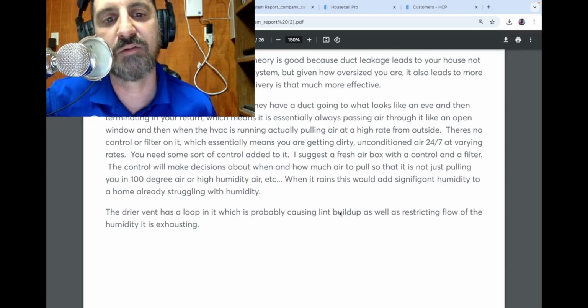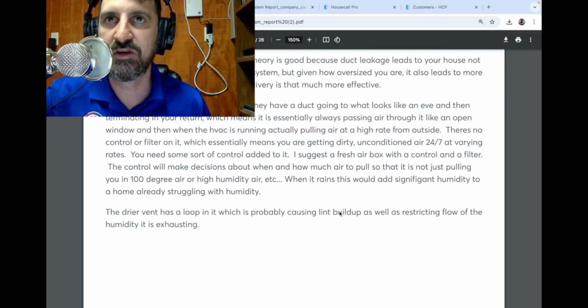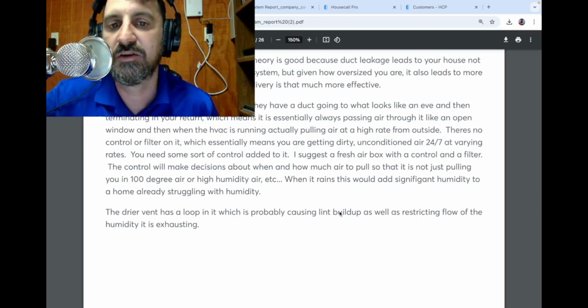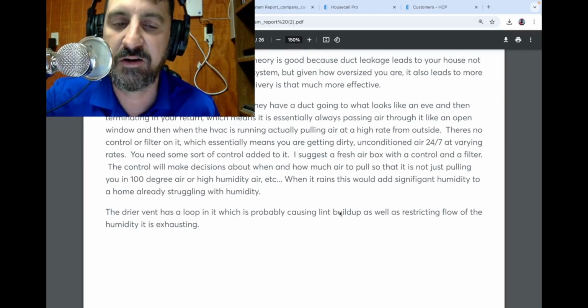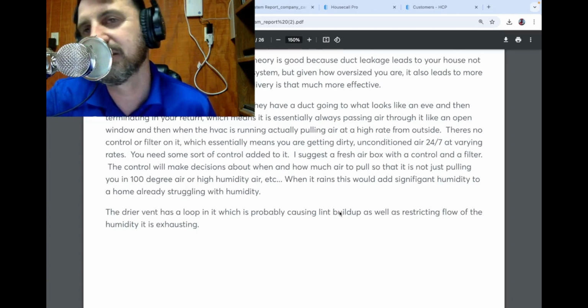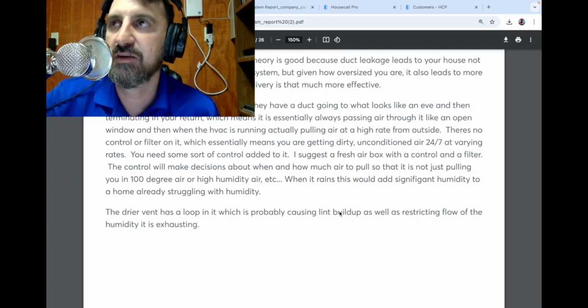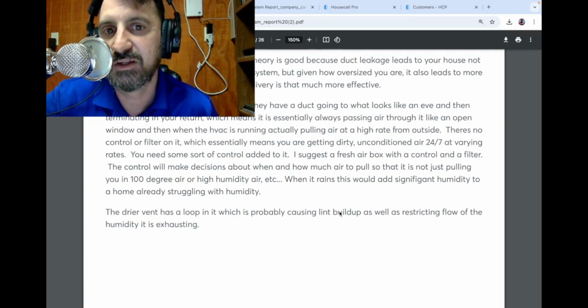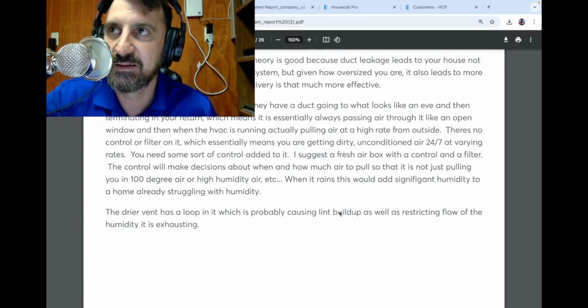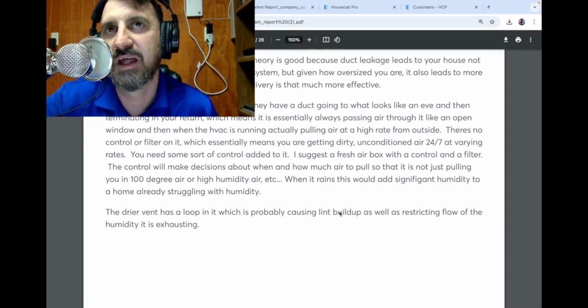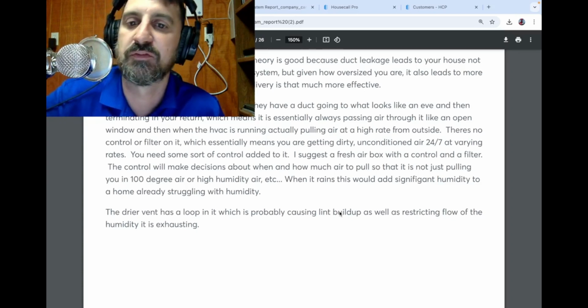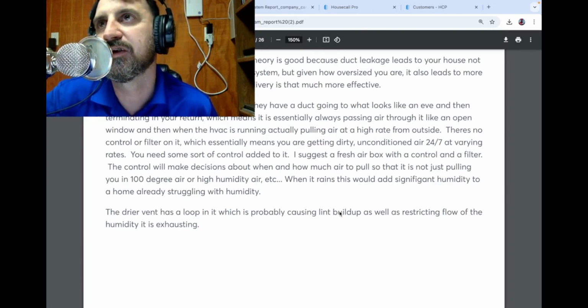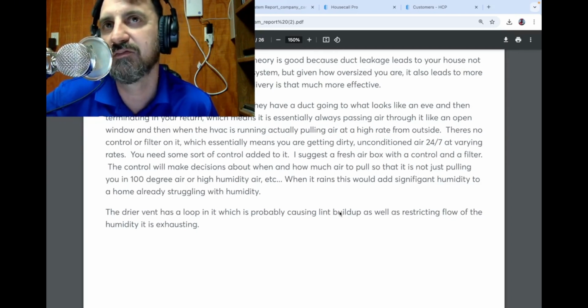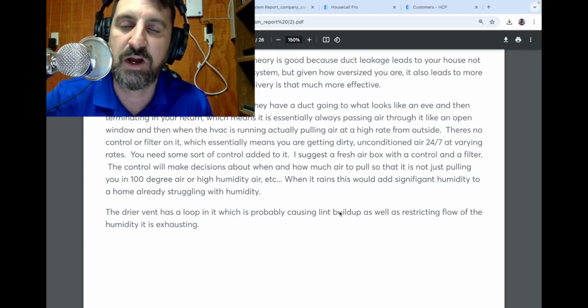So you have that air drifting in. Once the unit turns on, you're pulling 100 and some CFM through there, and it is unconditioned, unfiltered air. So if it's 105 outside, you are pulling 105 degree air, if not hotter, coming out of an eave like that. And if there's wasp nests, whatever built in there, you're pulling all that dirt and everything with it. It's not filtered before it hits the system. The filters are in the ceiling of the home, not at the unit, so it's not even filtering it before it hits the coil and supply.